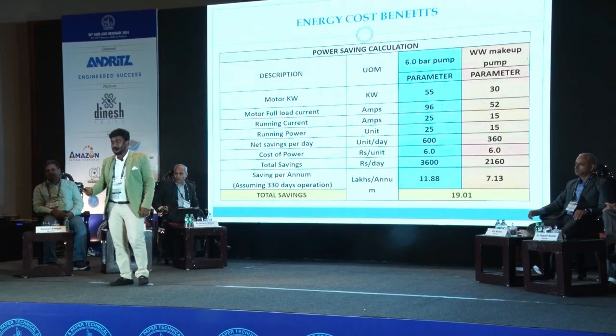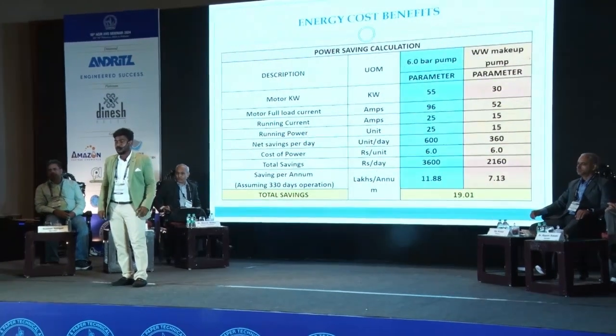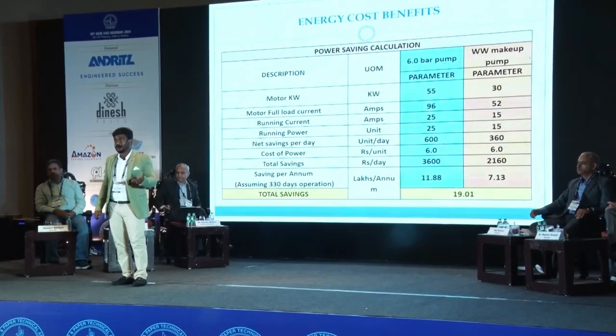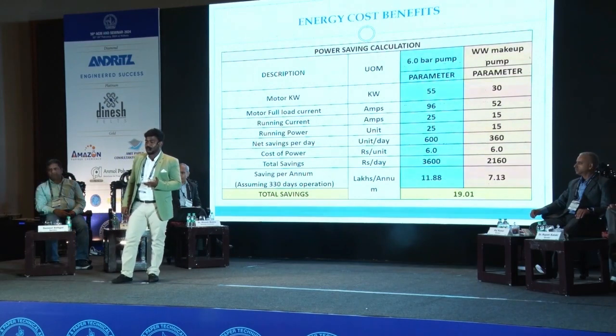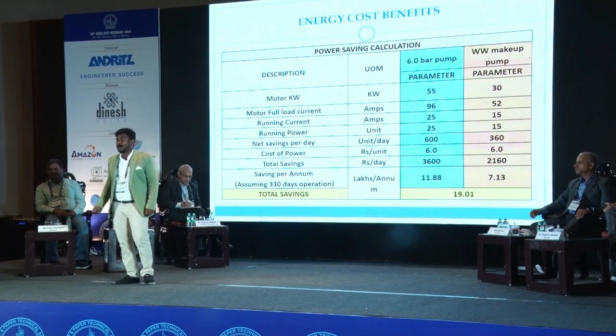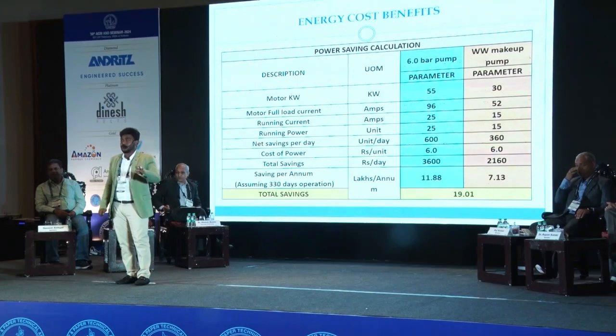So, the energy cost benefits from swapping these two pumps: the 6-bar pump is a 55 kilowatt motor and the white water makeup pump is a 30 kilowatt motor. Both are running at 25 amps and 15 amps. So saving 600 plus 360, 960 units per day. That gives us around 11.88 lakhs per annum for the 6-bar pump and 7.13 lakhs per annum for the white water makeup pump. So that gives us around 19 lakhs per annum savings by stopping these two pumps without affecting the existing paper making process.